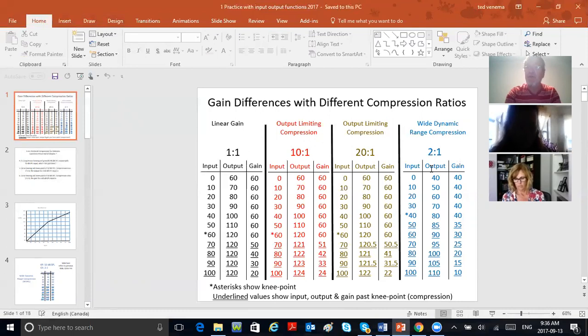And it emerged when the knowledge of outer hair cells became distinct from that of inner hair cells. It's also when otoacoustic emissions began to be done by clinicians, because we figured out that the outer hair cells help inner hair cells pick up soft sounds. So with outer hair cell damage, let's have a type of compression that imitates what the outer hair cells used to do. And that's exactly what wide dynamic range compression does. It imitates outer hair cells.